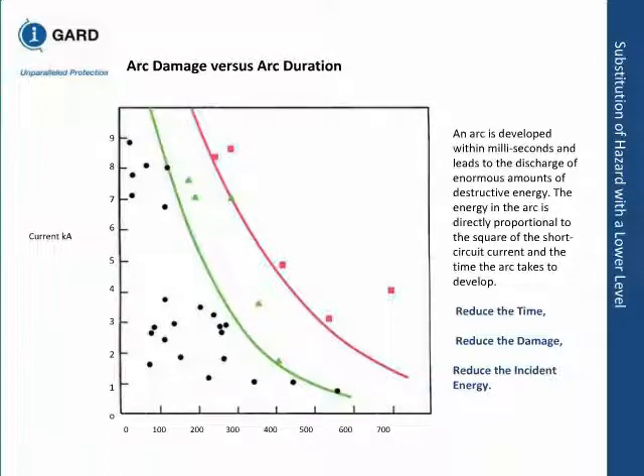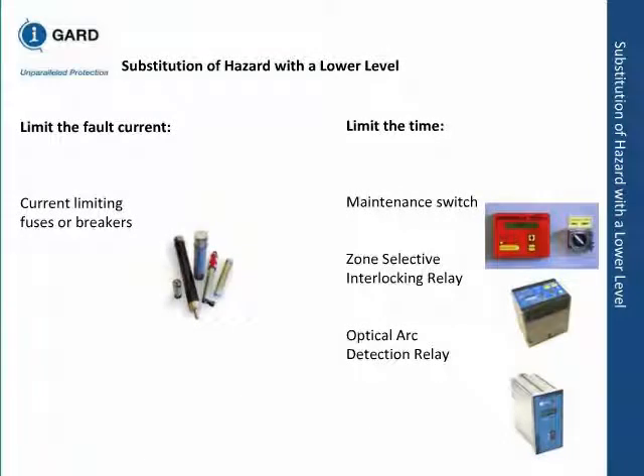So how do you substitute a hazard with a lower level? We have all accepted electricity is a hazard. You can limit the time the fault persists before you clear it out. It could be done by a maintenance switch, or you can use current limiting fuses or breakers. Now, you have to be careful. Current limiting fuses or breakers are only limiting in the current limiting range. Every fuse is not current limiting. Every breaker is not current limiting. So current limiting fuses or breakers will reduce the time. So will a maintenance switch, and we'll explain that.